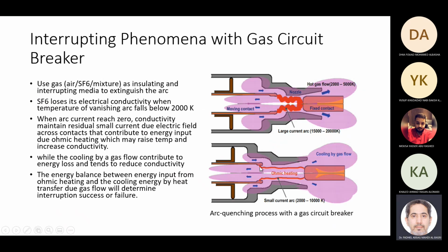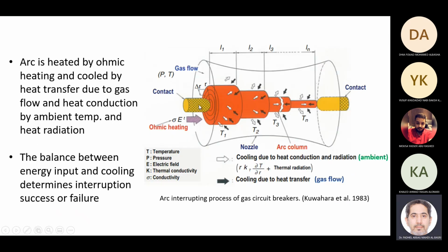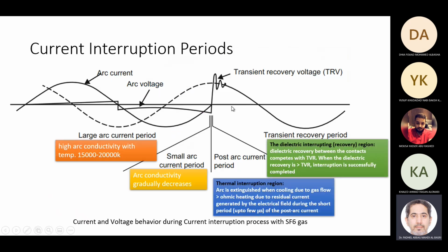But these breakers also have to be very fast when you open. So this is the arc. When you open it, there is ohmic heating from the current, and there is cooling energy from the gas and from the ambient temperature. So this is the theory.